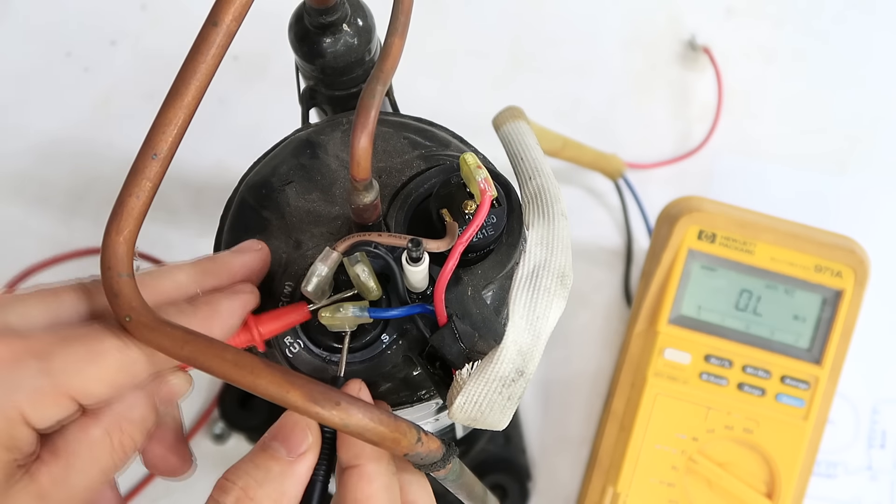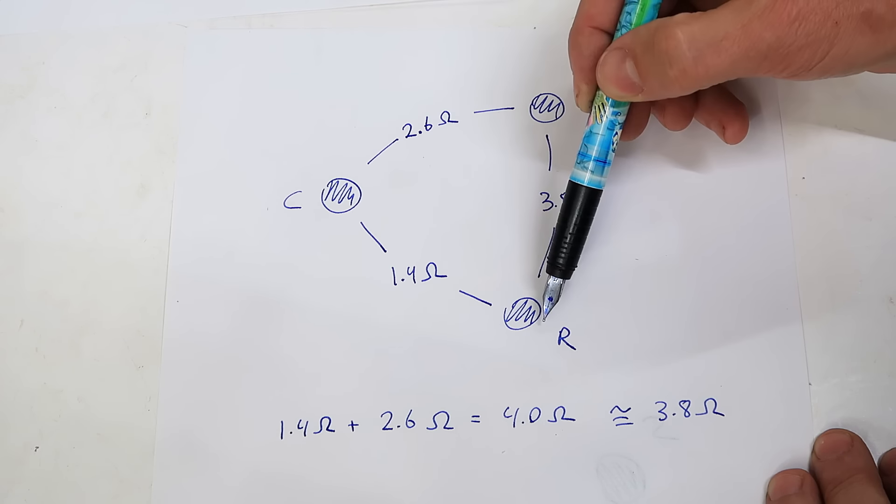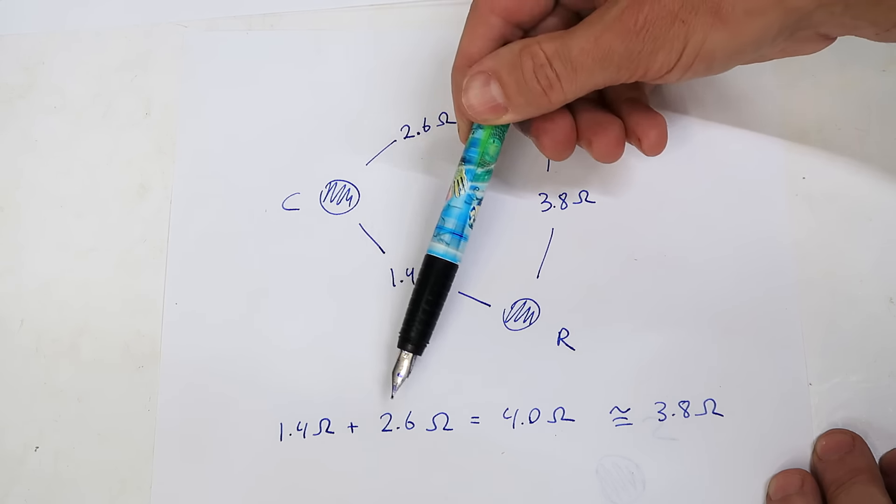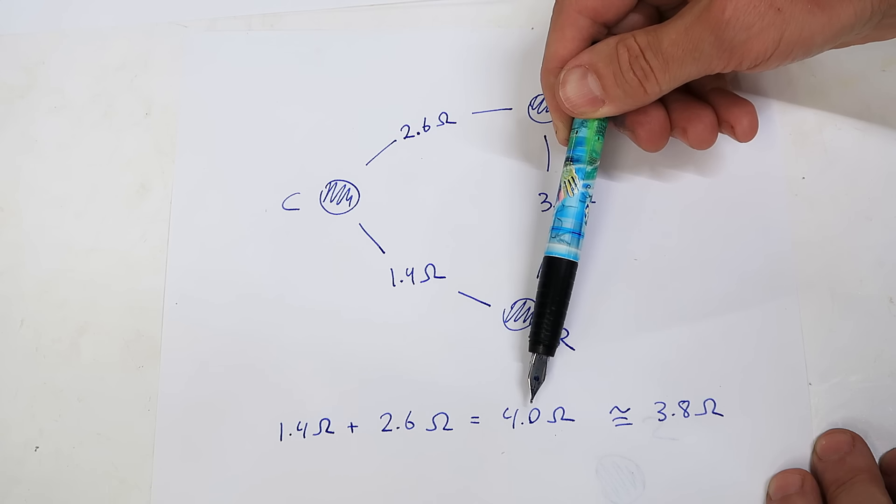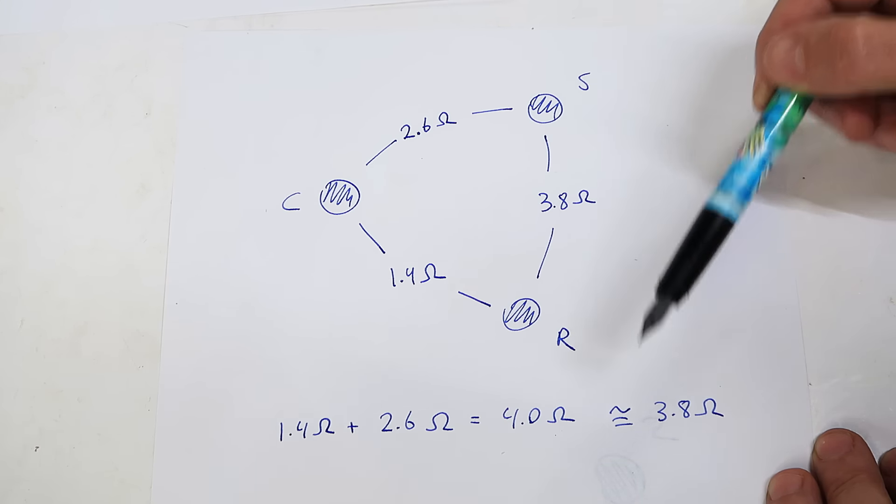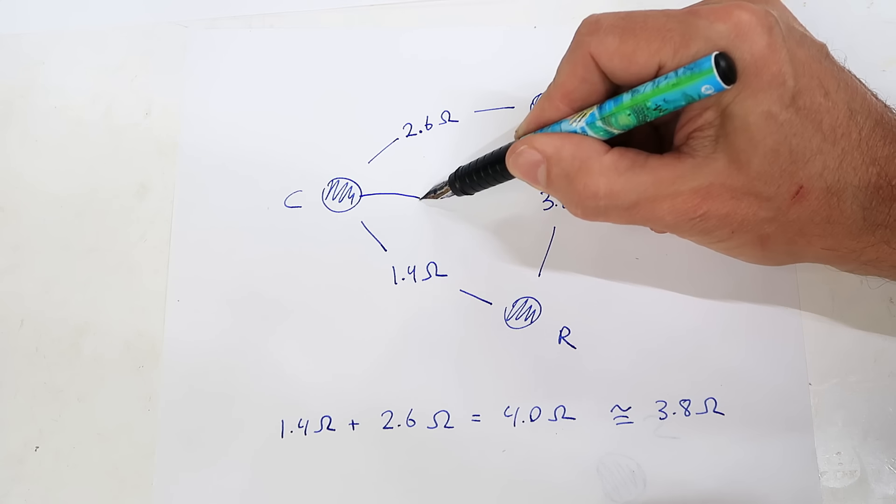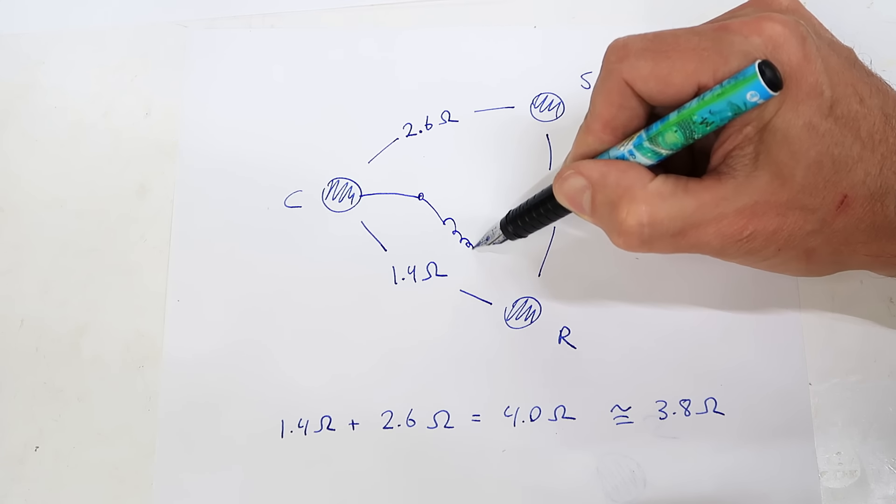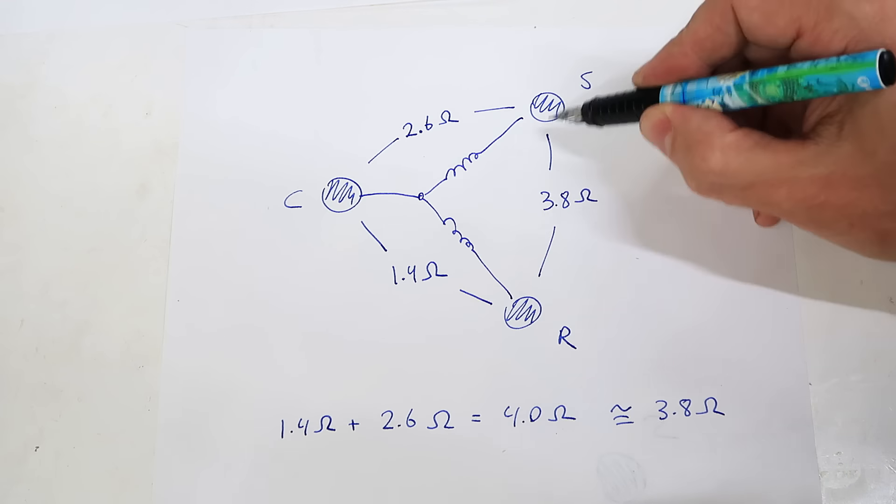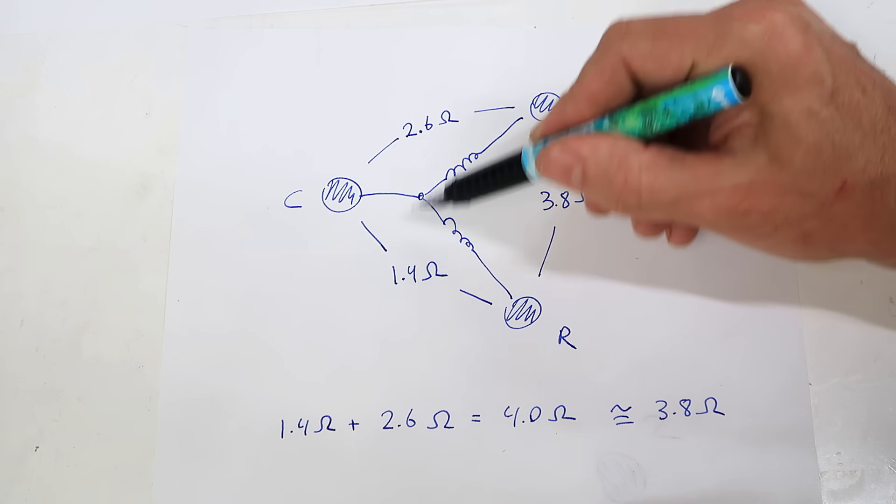I measure the DC resistance between the three terminals. Between C and S I get 2.6 and then 1.4 to R and S to R is 3.8 ohms. Basically the 1.4 plus the 2.6 ohms is 4 ohms, which is pretty close to the 3.8 ohms I'm getting across here, especially because the meter always reads about 0.1 ohm high. That tells me that internally I've got basically a winding going here and a winding going here, and if I measure between those two here I essentially go through both of those. That resistance is this one plus this one.